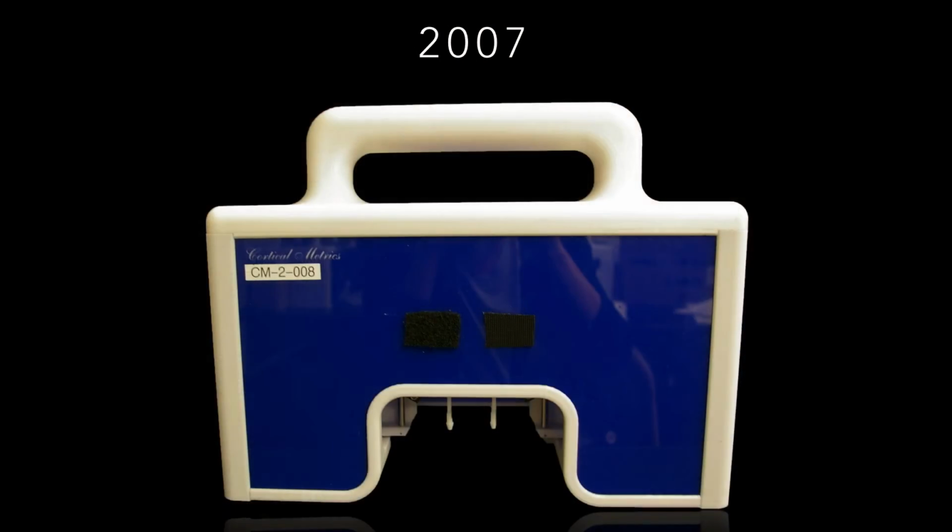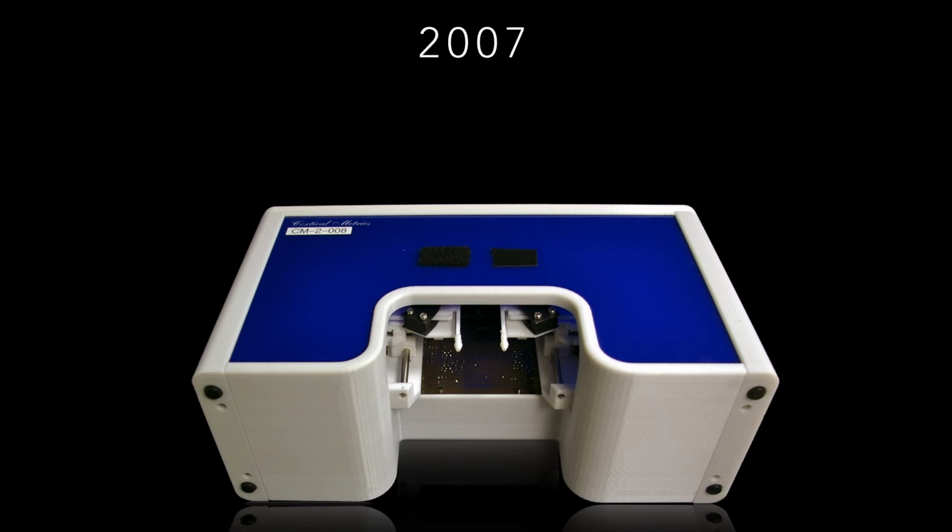As far as the mechanical design is concerned, we had very stringent challenges because it has to interface with a human being, and it has to be able to measure displacements less than a micron. It has to have extremely high fidelity frequency-wise. The frequency has to be exactly correct. And there's really nothing commercially available that can do that. So we had a very difficult parallel development task for this product.